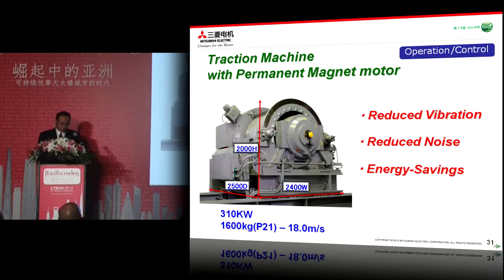Applying a permanent magnet motor for such high speed elevators, we could achieve reduction of vibration and noise, and energy saving. This is a picture of the traction machine for the world's fastest elevator at 18 meters per second, which has a rated output of 310 kilowatts, using a double three-phase winding motor and parallel drive system with two control panels. The traction machine is approximately 2.4 meters wide, 2.5 meters deep, and 2 meters in height.